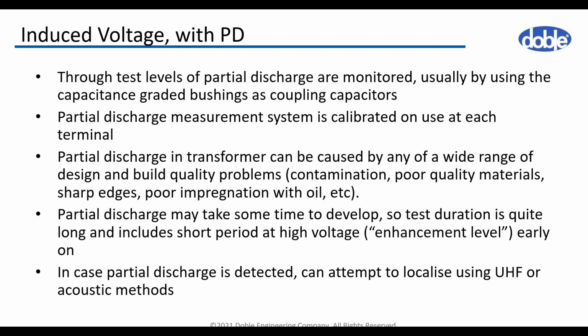As I already noted, partial discharges are monitored using the test tap of the capacitive graded HV bushings as coupling capacitors. Partial discharges are an important indicator for design and quality problems of the insulation system, including contamination, poor quality materials, sharp edges, or issues with the oil impregnation. Sometimes it requires time to develop partial discharge activity, so the duration of the test is relatively long, with an enhancement level of a very high voltage.